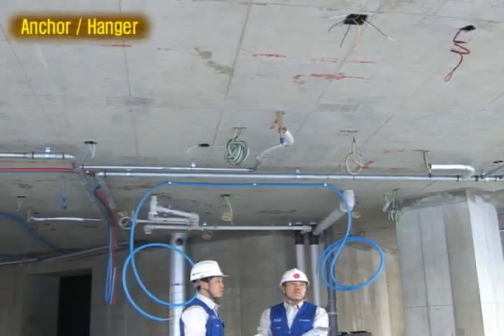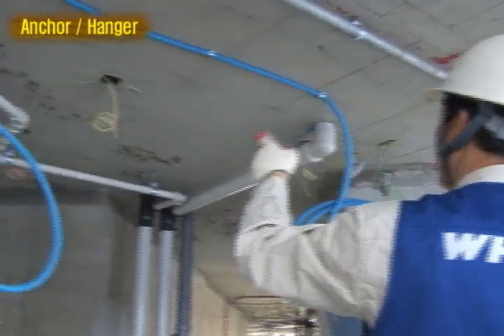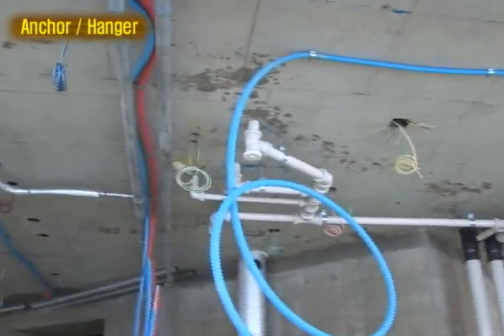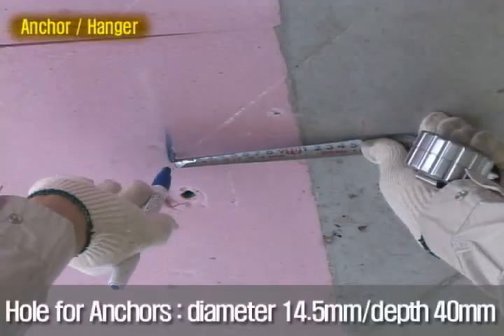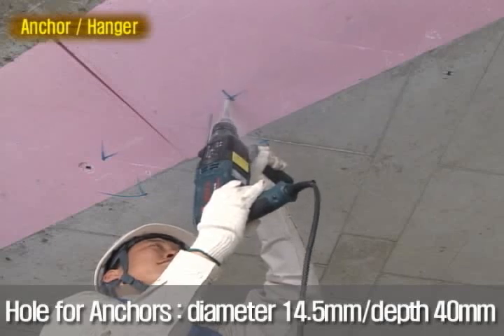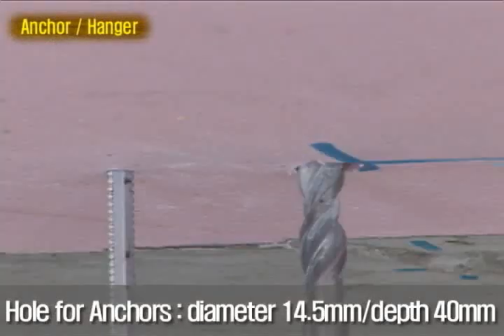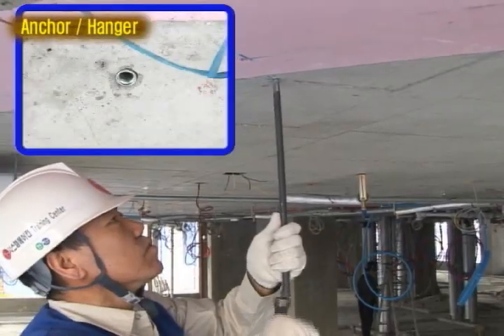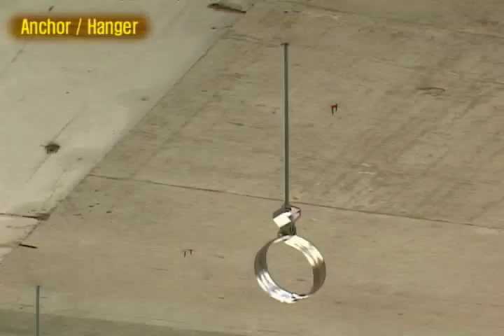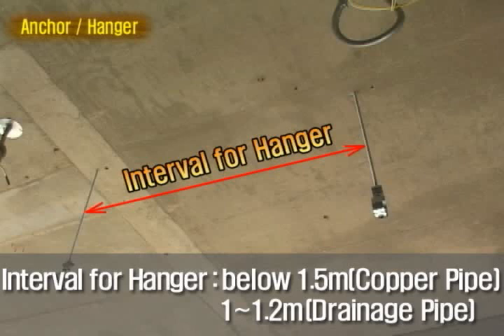It's more convenient to arrange hangers for the pipelines and cables before the ceiling construction. Make a hole of 14.5 millimeters diameter with 40 millimeters depth at the point of the pipe's installation. Install a wedge anchor and attach a hanger. The hanger interval should be less than 1.5 meters for refrigerant and 1 to 1.2 meters for drain pipe.